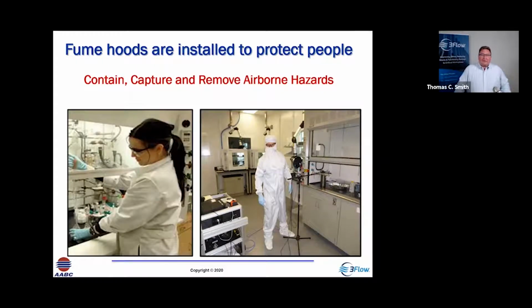So recognizing that fume hoods are installed for one singular purpose, and that's to protect people. They are the primary safety device used in laboratories to protect people. So we have to ensure that not only are they functioning properly, but they're operating at the appropriate face velocity, but they're actually protecting people from exposure. So we have to move beyond just face velocity testing. We have to evaluate how it is functioning from a performance standpoint to protect people from exposure. So that job of the hood is to contain, capture, and remove airborne hazards.